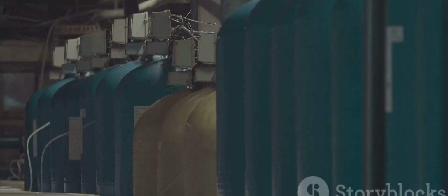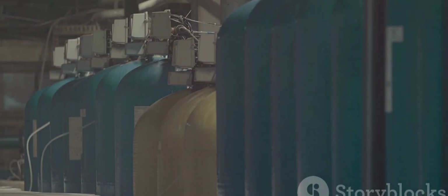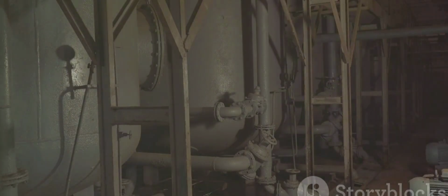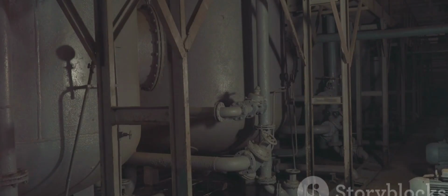Filtration. The process of filtration is used to remove remaining suspended particles, turbidity, and microbes. The clarified water is passed through filters made of materials such as sand, gravel, and activated carbon. These layers trap any remaining contaminants. Key parameters include filter bed depth, filtration rate, which is measured in cubic meters per hour, particle removal efficiency, and filter backwash frequency.